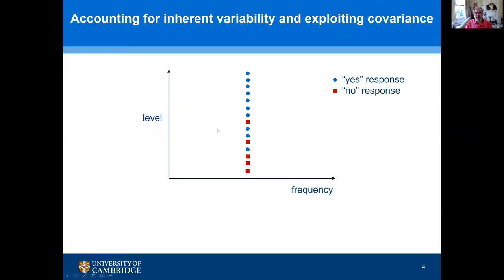Here's an illustration of a basic problem in estimating the audiogram. There's inherent variability in the responses of subjects. Imagine you present a signal with a fixed frequency at various different levels. When the subject says yes, that's indicated by a blue symbol; when they say no, that's indicated by a red symbol. There's a region where responses are mixed — if you present the sound repeatedly at one of these levels, the subject will sometimes say yes and sometimes say no.